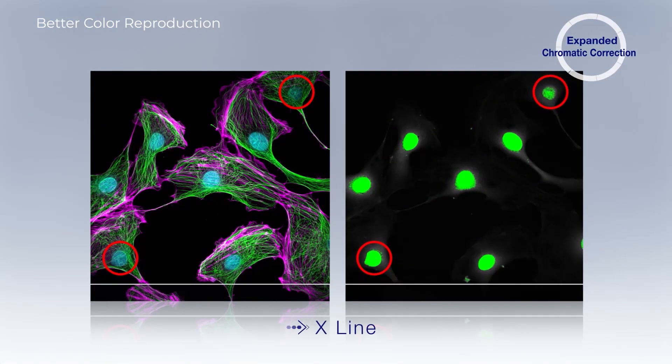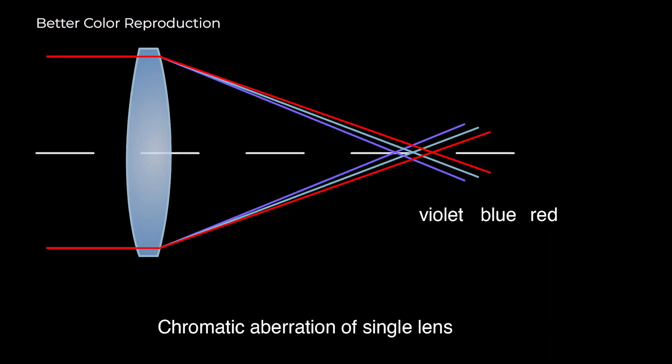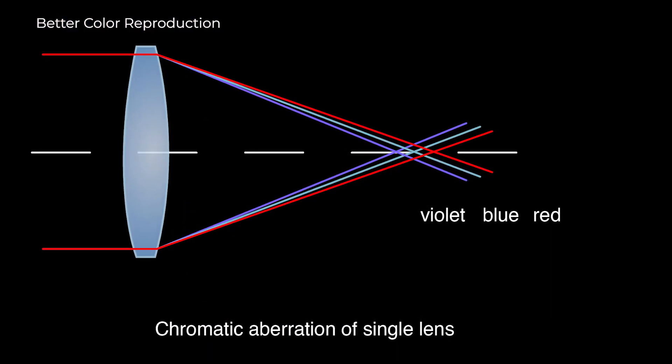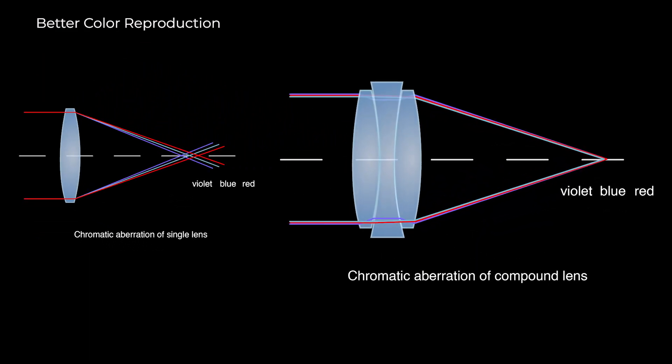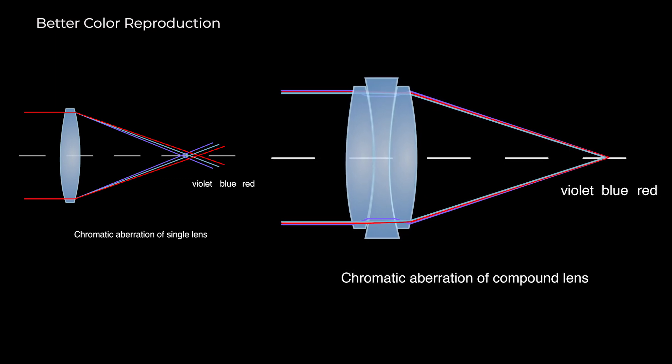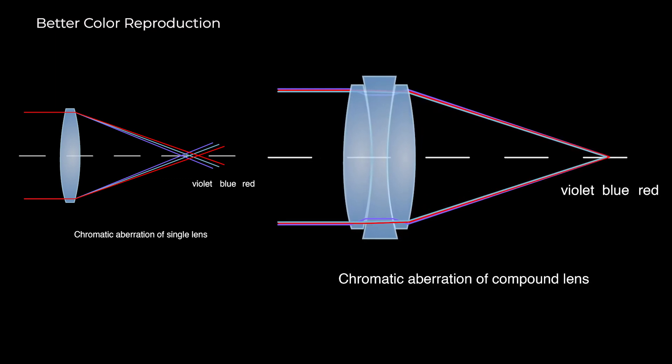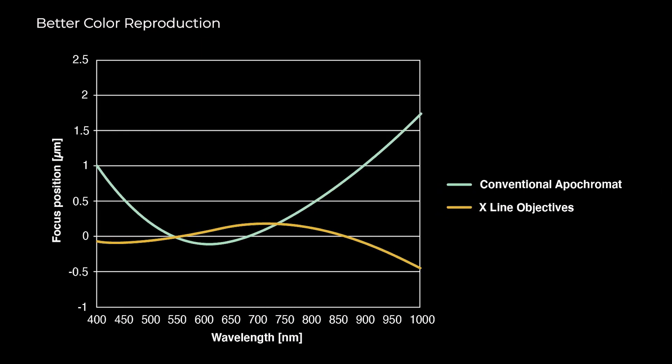Chromatic aberration is caused by glass that has a different refractive index for each wavelength. Generally, the refractive index of glass is higher for shorter wavelengths. Optically, you can correct for chromatic aberration by combining convex and concave lenses so that red and blue light focus on the same position. Now that we can fit more optics in a single objective, corrections are improved from 400 to 1,000 nanometers.